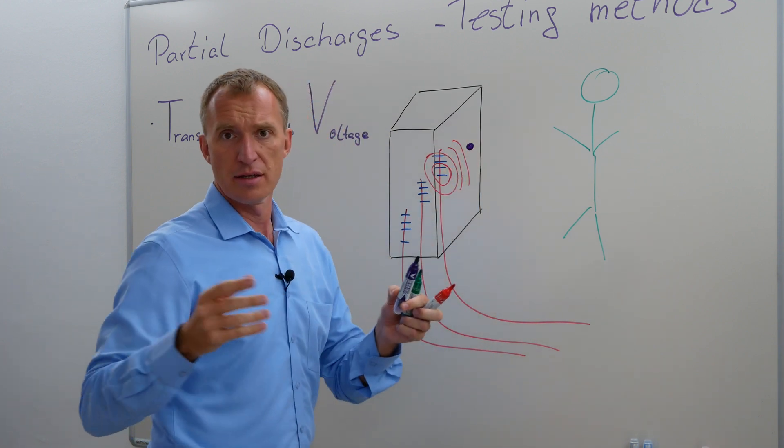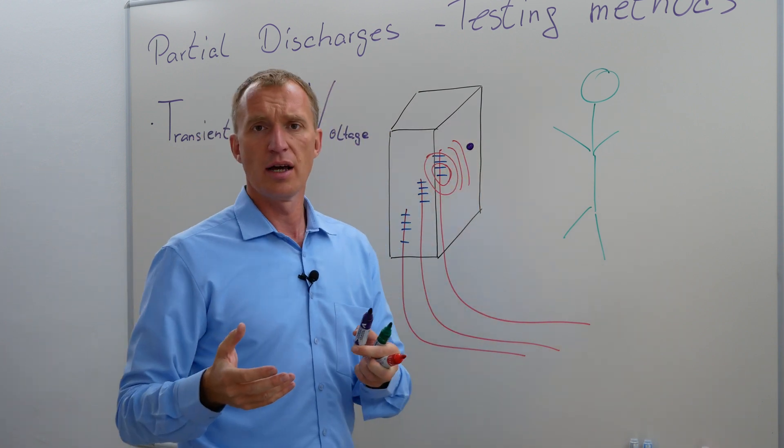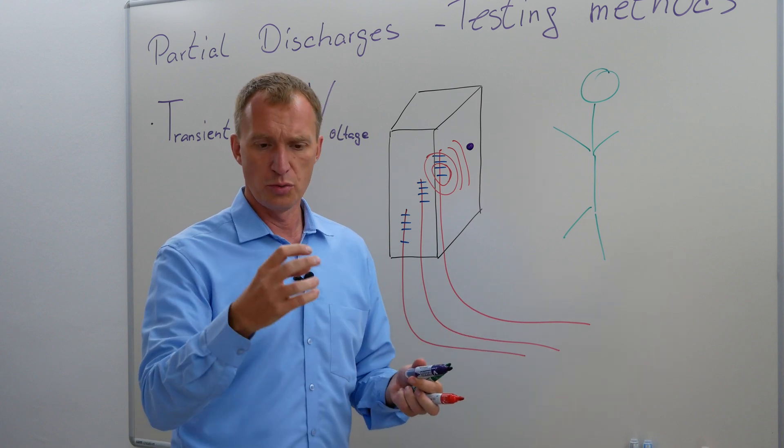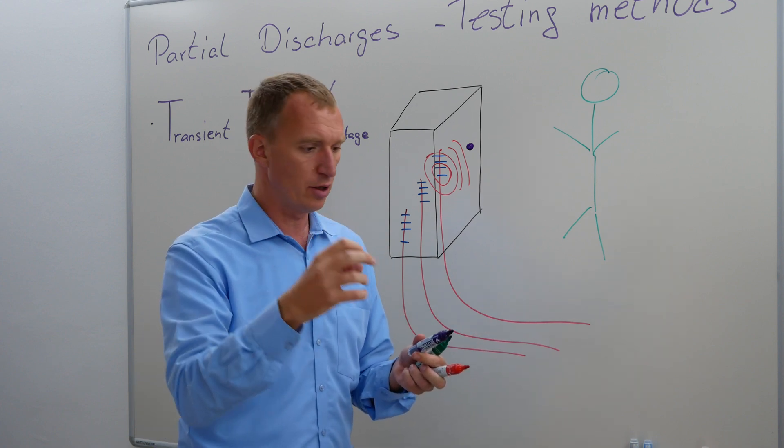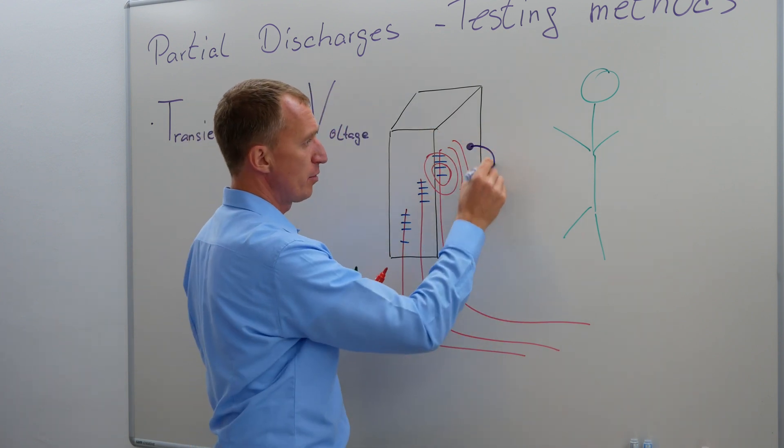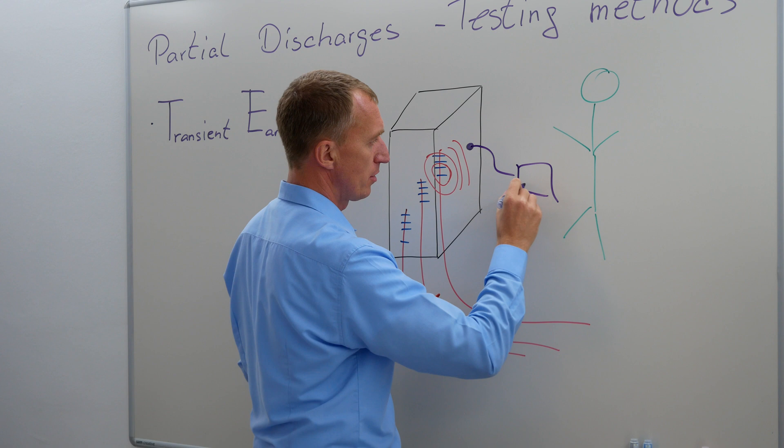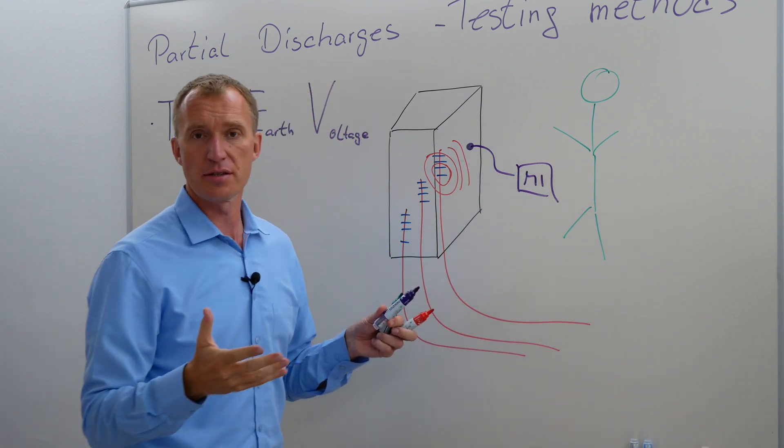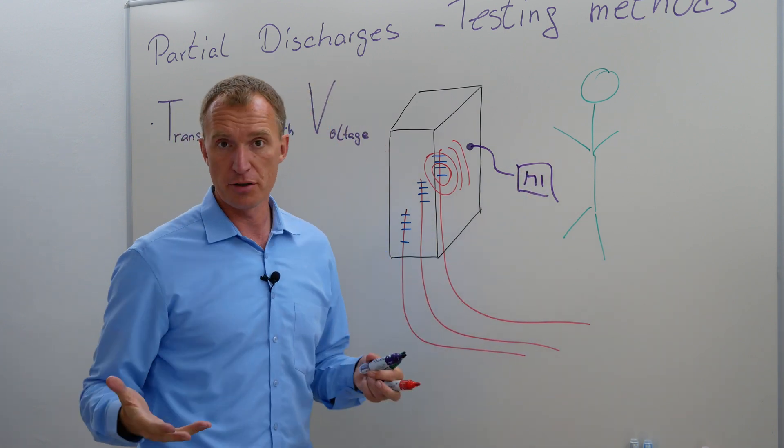They are usually capacitive sensors and there are quite a couple of manufacturers who produce them already with a magnet on it. So you put that on and you have a cable, and then you have a device, your measuring instrument, and then you can see if you sense any partial discharge or not.